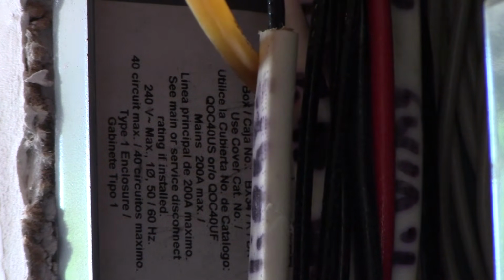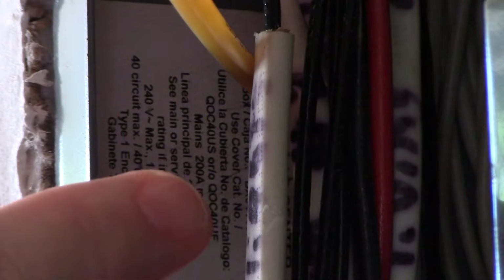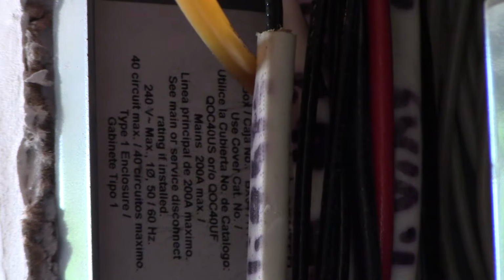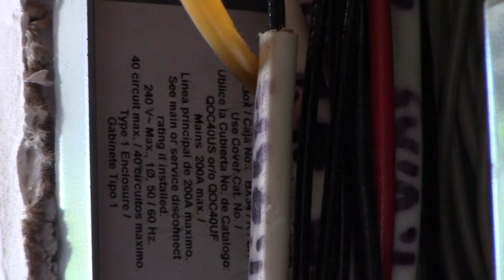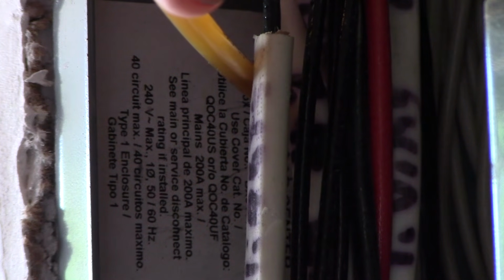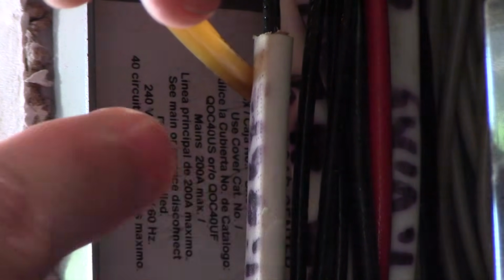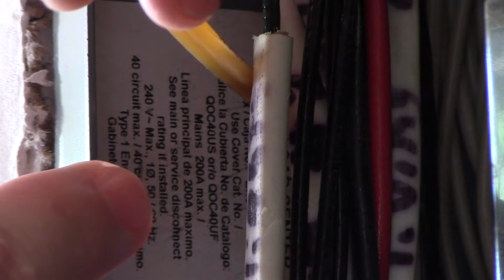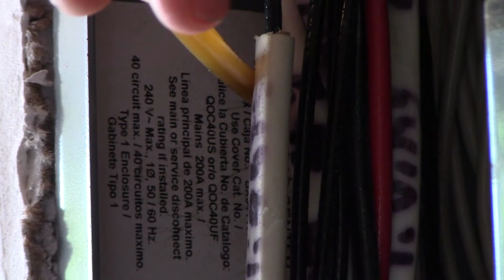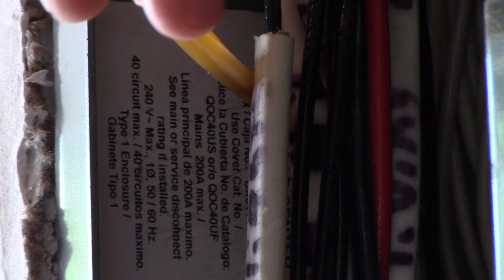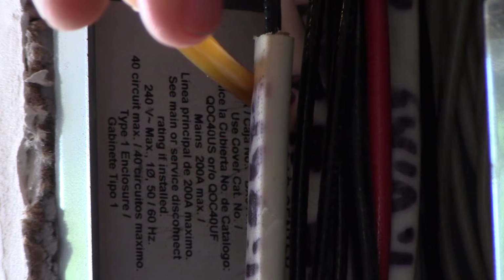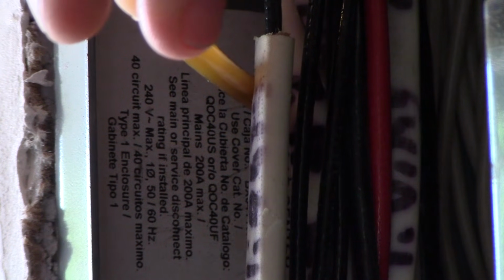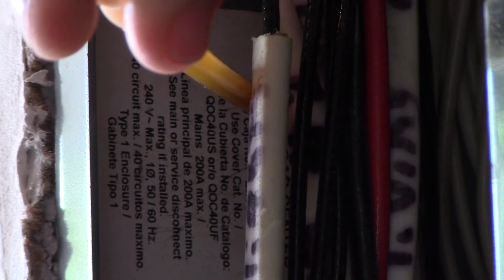All right. We also notice that it says 240 volts. Okay, so we've got that right here. So we know that's a 240 volt, and we know it says it's a 40 circuit panel. It does say it's a type 1 enclosure. We do see that it's single phase because we have that marking right here, right above my finger. We see it says 1 aught. One phase. That's a phase symbol. And we see it says a maximum main is 200 amps.